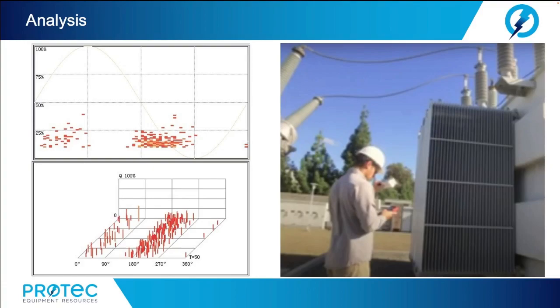Now, phase-resolved partial discharge patterns are a method of comparing the incoming signal to the AC power frequency. The PRPD charts are shown in real time. The horizontal x-axis is the phase angle of the power system under test. The x-axis is labeled from 0 to 360 degrees. This is the same thing as 0 to 16.66 milliseconds. This is the time it takes for one cycle of the AC power frequency. The vertical axis, or y-axis, represents the amplitude of the signal. The amplitude depends on the strength of the signal and on the distance from the sensor to the PD event.